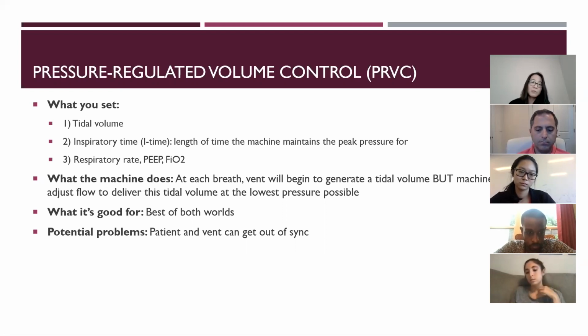Potential problems, the patient and the vent can get out of sync. For example, if the patient's demand increases, then all of a sudden the machine is going to be like, wow, this patient is just sucking this air in. I barely have to generate any pressure to deliver this tidal volume. And then that pressure is going to go lower and lower and lower to the point where the machine isn't even helping the patient breathe at all. So it's the best of both worlds, but also not foolproof in terms of just clinically what's going on with the patient.